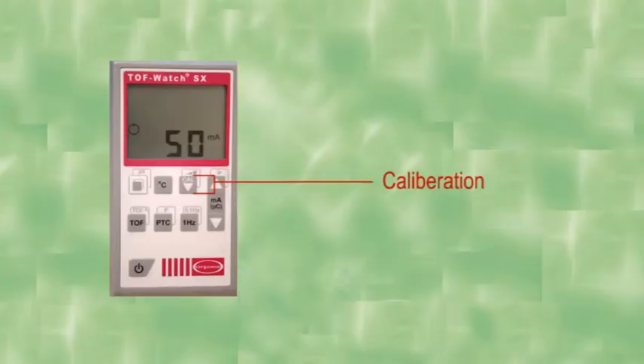The next button on the equipment is the calibration button. We know that the resistance of skin of various patients are different. The differing resistance may offer differing currents to the patients and the misinterpretation of results may occur. In order to avoid this, every time TOF-Watch is used, it has to be calibrated. A long press of this button leads on to adjustment of 100% twitch height. After adjusting the 100% twitch height, it returns to the basal. It is important to use this when we are dealing with special patients such as neonates or obese patients or elderly patients.